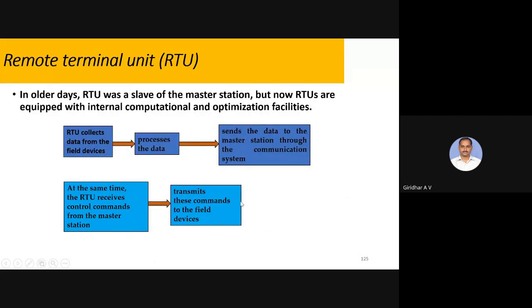In olden days, the RTU was a slave of the master station, but nowadays additional features have been added to the RTU. Advanced and computational techniques have been added for better computations, and passing into the master station so that appropriate actions will be taken. This RTU collects data from the field devices, processes the data, and sends the data to the master station through the communication system. At the same time, the RTU receives control commands from the master stations and controls the field devices. Both things happen through the RTUs.